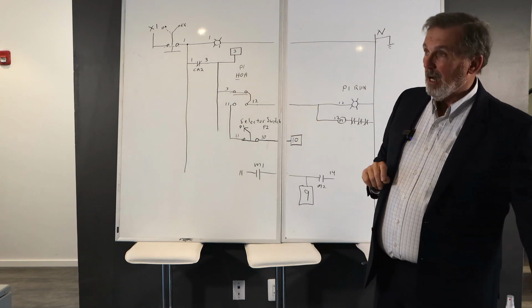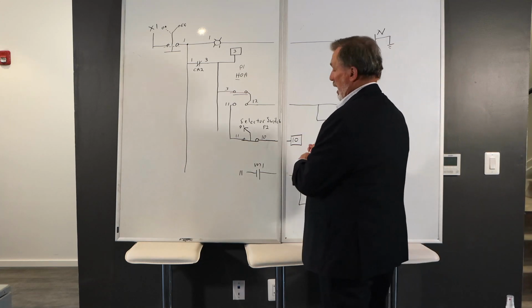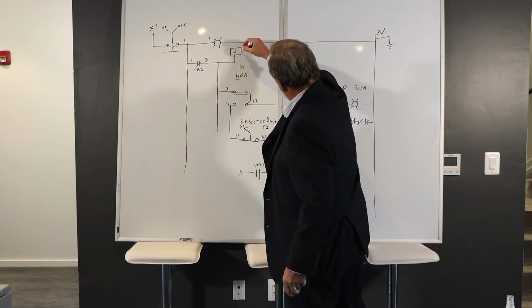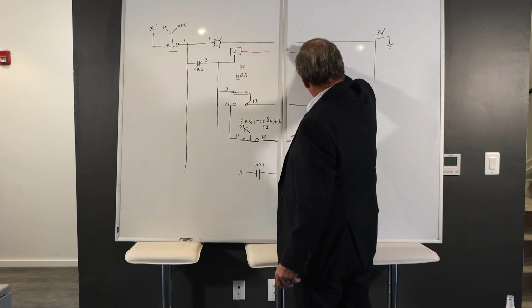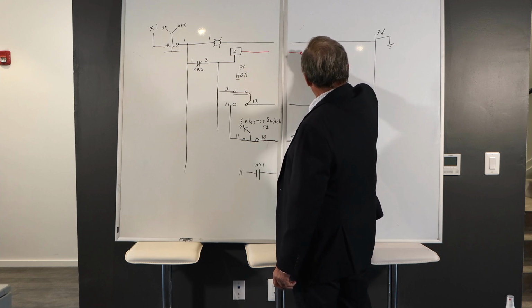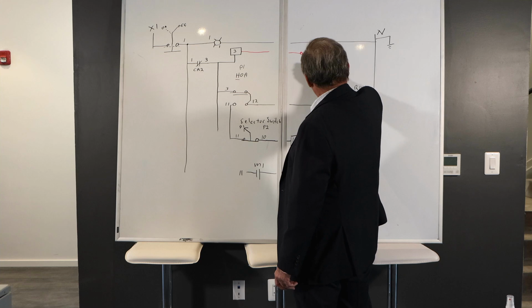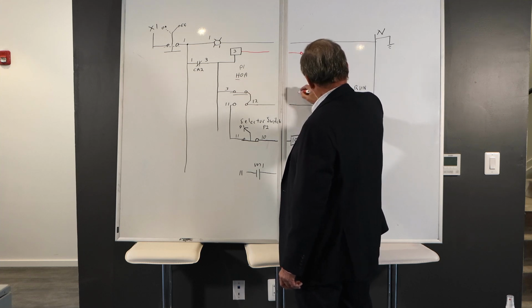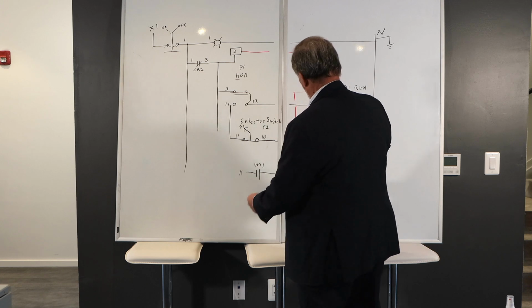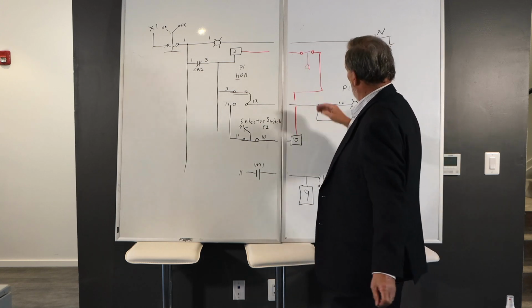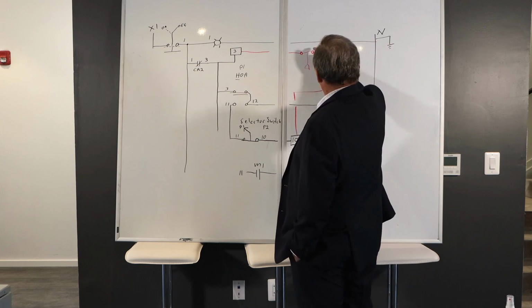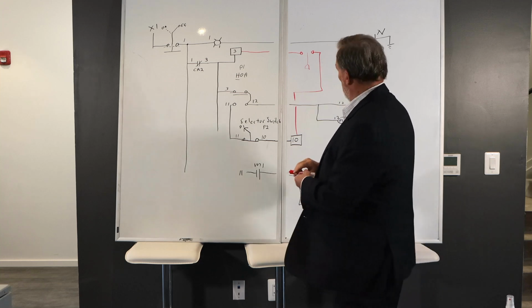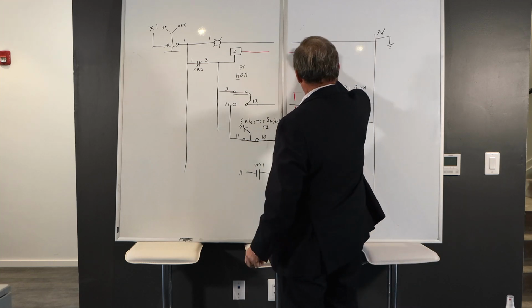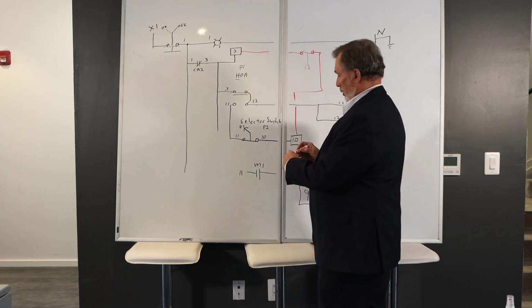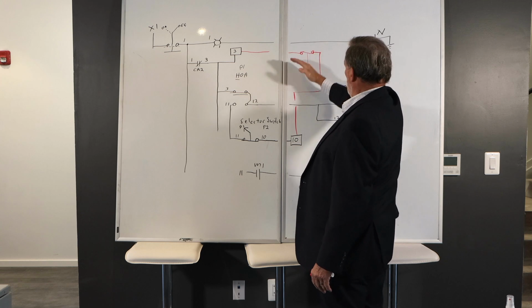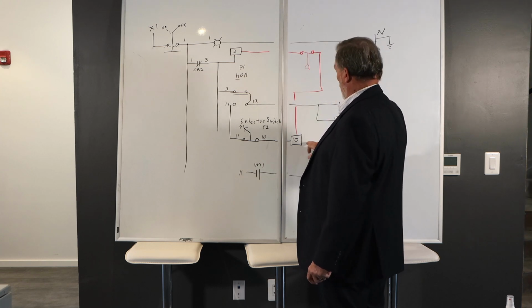an external contact. So I'm going to have a contact from 3 over to a level switch, and then from there down to 10. Okay? The level switch indicates that the water level, I should have drawn this differently, I'm sorry. The level switch, it tells me when the water level is low, it tells the pump to come on. Okay? When the water level drops, 3 drops out, okay? Shuts down the feed on 10.